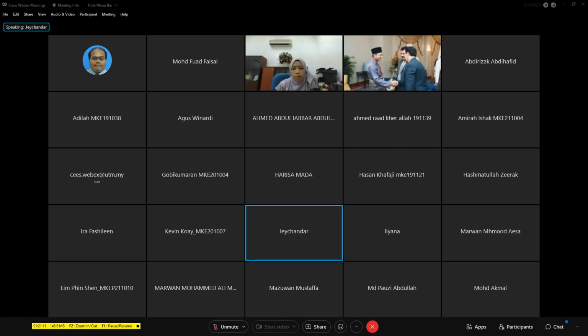First of all, for EMC there are 3 levels. The one that I've experienced now on the voltage sag and harmonics is the first level, called low frequency, meaning events with frequency less than 9 kilohertz. For TNB, we notice this is the most critical EMC issue for customers. That's why inside our handbook and guidebook, we mention the customer must have immunity and emission control on this low frequency EMC. The one you are mentioning is the medium and high frequency EMC. The medium is around 140, 150 kilohertz, and the highest is more than a few megahertz. That one is not from TNB, it's from your equipment requirement.